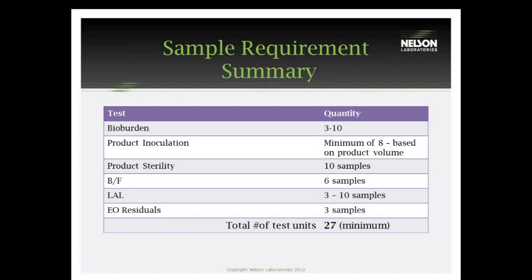In summary, for the total amount of samples you will need: the minimum total is 27 samples for a one cubic meter load or less. That includes 3 samples for bioburden, 8 samples for product inoculation, 10 samples for product sterility, 6 for BF testing, 3 for LAL, and 3 for residuals. The 6 samples for BF testing can come out of the 10 samples for product sterility, and we actually recommend that because then the samples go through the same testing process for both product sterility and BF, easily validating that test.